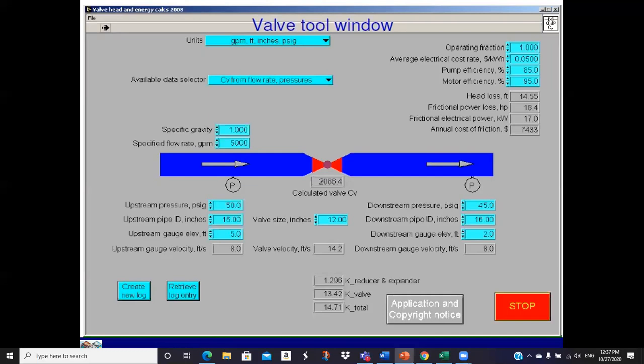So this is a fairly common scenario. We're showing a 12-inch valve and 16-inch pipe. We've got 16 up and 16 down. We've got our differential pressure. It looks like we're dropping 5 PSIG. It's possible that this pipe could be running up and down vertically and have a change in elevation. So the upstream gauge is 5 feet and the downstream gauge here is 2 feet. So that impacts the analysis. And then you get a calculated velocity. We're at 8 feet per second. Is this wide open? Not sure about that valve velocity, but I think that would be at 12-inch diameter, I'm pretty sure. And then we're at 8 because we're back to 16.